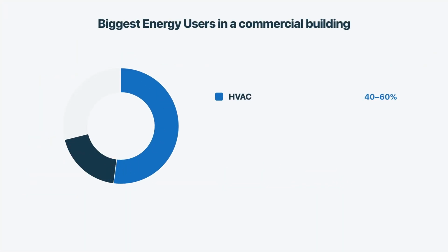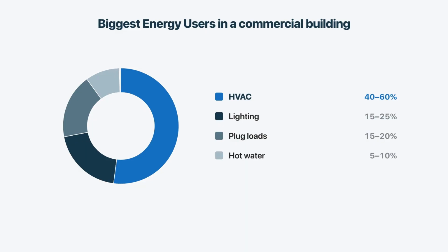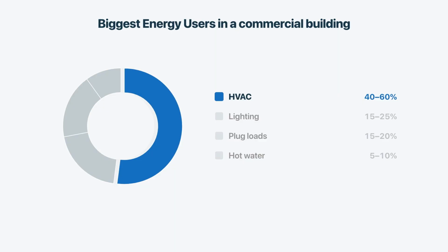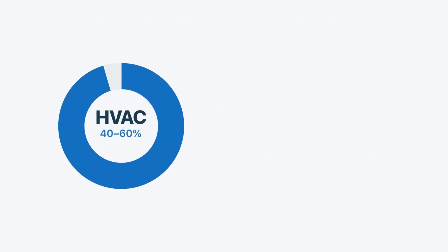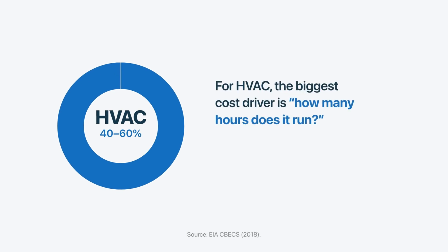Let's dig in. HVAC runs between 40 and 60% of total energy use in a typical small commercial building. According to EIA's Commercial Buildings Energy Consumption Survey, or CBECS, HVAC is the largest single end use by a huge margin. Everything else, lighting, plug loads, hot water, is a smaller share. Which means the single biggest lever you have on energy use in a small building is how many hours the HVAC system runs for. Not how efficient the chiller is, not how well the envelope is insulated. Those do matter. But the first order variable is runtime.